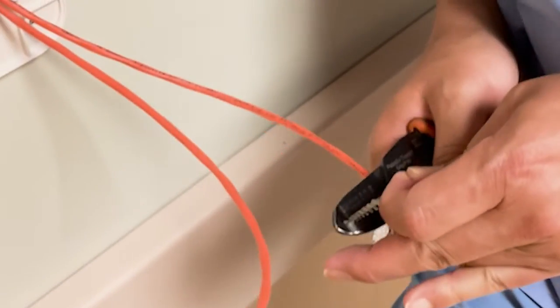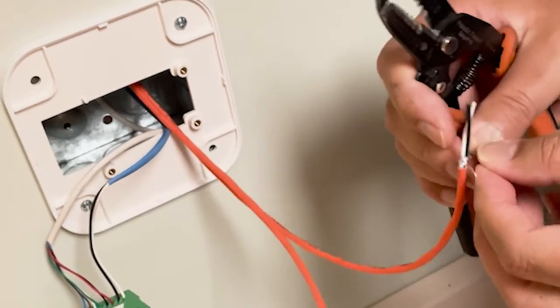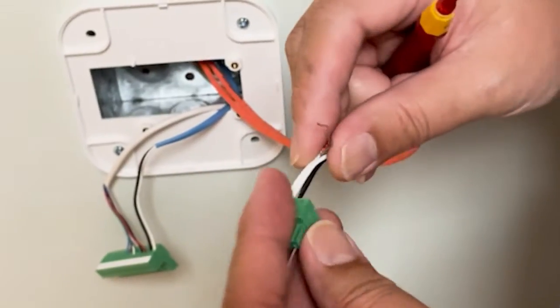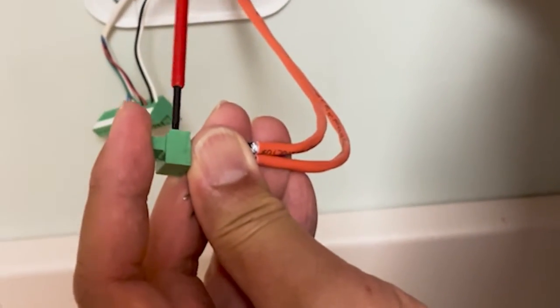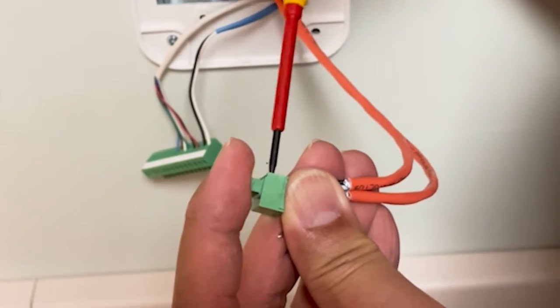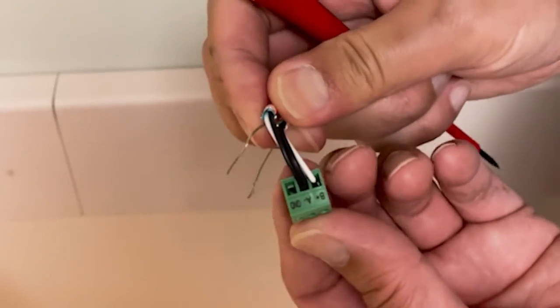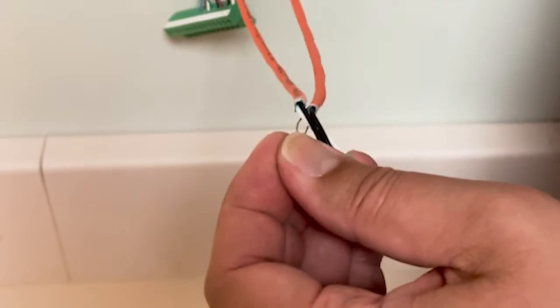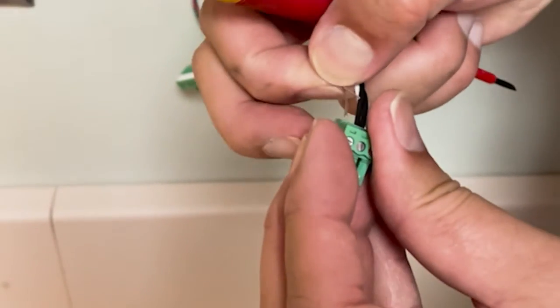We need to strip all of our wires back before we can connect them to our connectors. We're going to connect the MSTP wires. Since we have an additional device downline from us, we have to connect two white wires, two in each one here for the MSTP connection. Standard MSTP installation. Note that colors are dependent upon how you connect on the other end at the MSTP trunk or at your previous device. You do not have to follow the color coding that we've done here, though what we've done here is common.